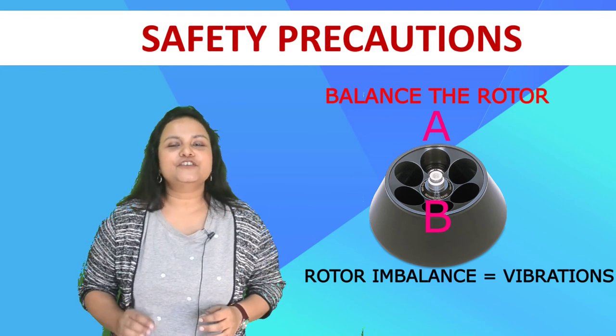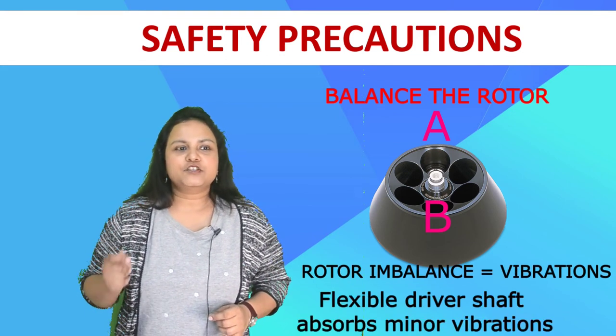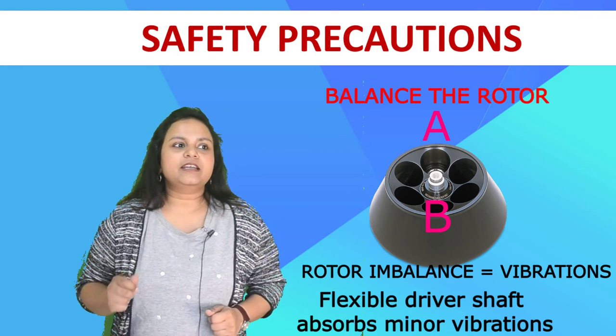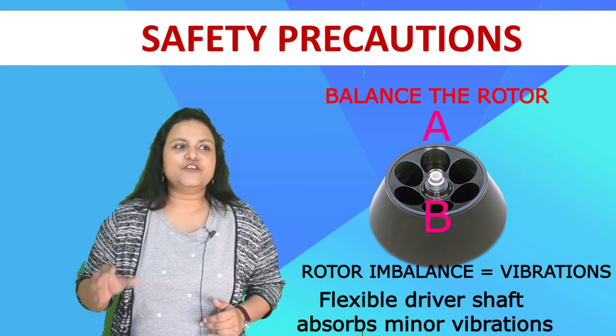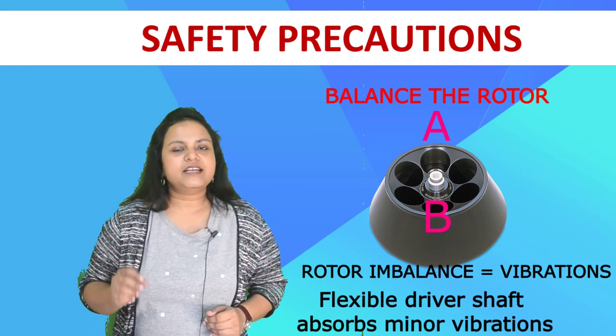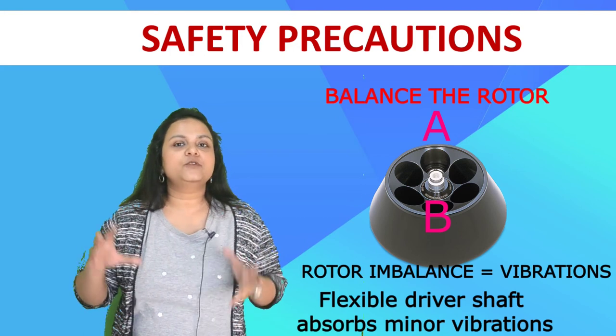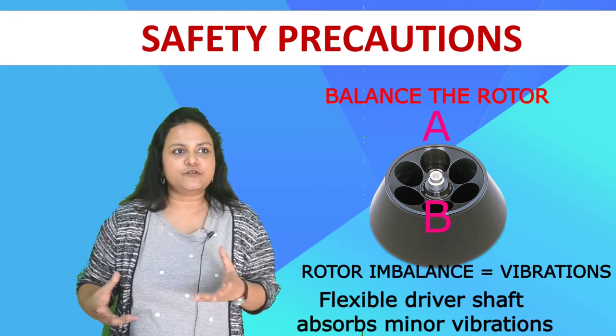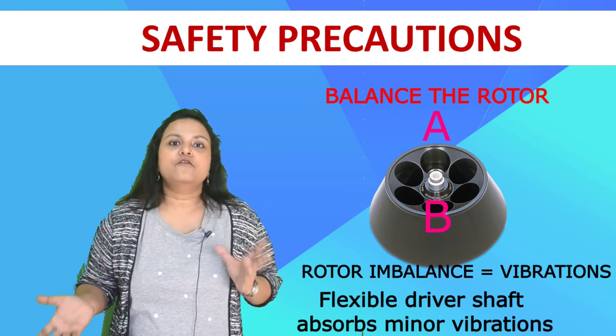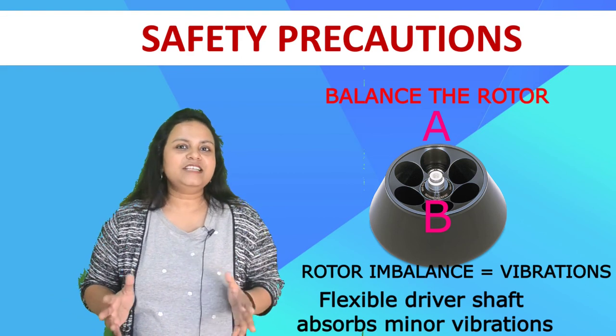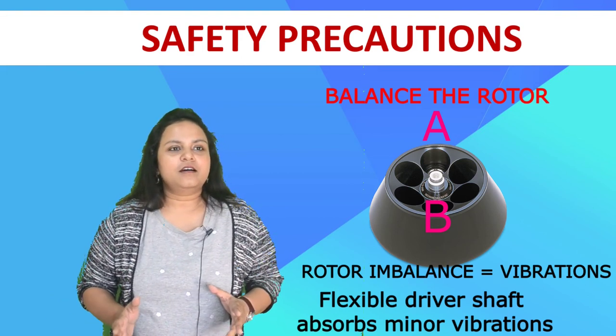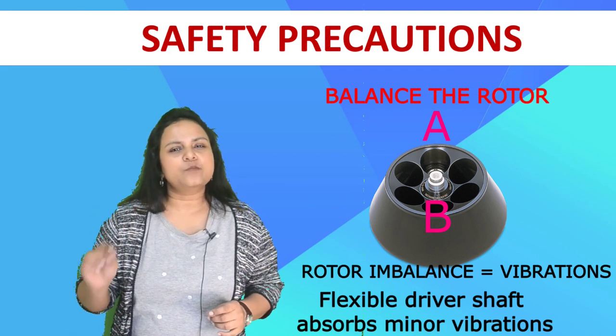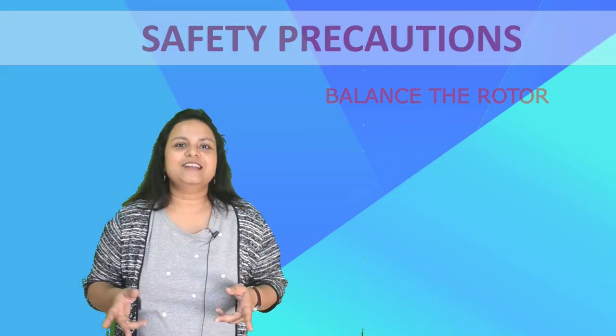Modern centrifuges do come with a kind of fail-safe. They have a flexible driver shaft, which absorbs or dampens any minor rotor imbalances and prevents vibrations from traveling to the framework of the centrifuge, thus preventing the centrifuge from wobbling overall. However, these driver shafts are not really meant for major rotor imbalances — only for absorbing very small, minor imbalances. So balancing your rotors remains essential.